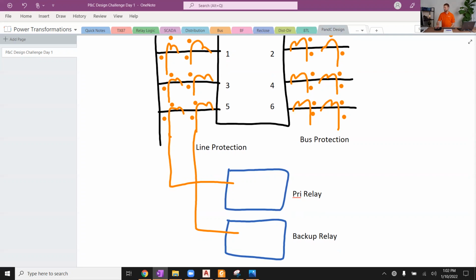And then I have a question from Hamad. Can you show examples of dead tank and live tank CTs? I do not have anything prepared on that as far as pictures. I'd have to Google search to find you some. I very rarely encounter live tank circuit breakers and live tank CT stands. That's maybe a 500 kV class at times. I've seen it out there on some of my client systems, but typically we're dealing with dead tank most often.